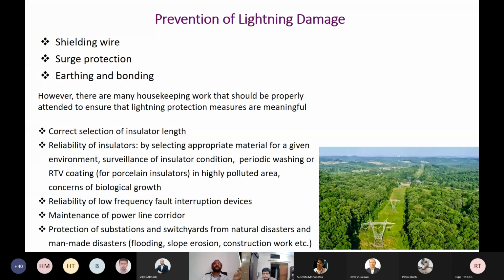Because there is no point in adopting lightning protection. Even the best lightning protection in the world will utterly fail if you do not consider the electrical safety measures that should essentially be taken. This is valid not only for medium voltage protection, but for low voltage system protection as well.